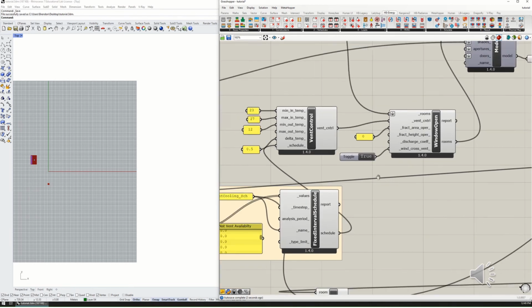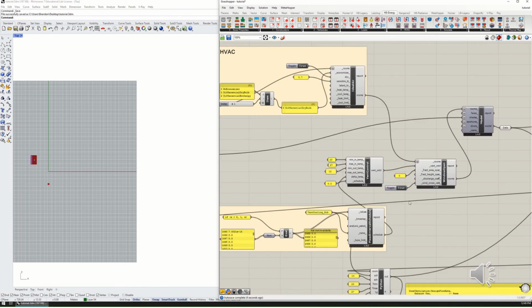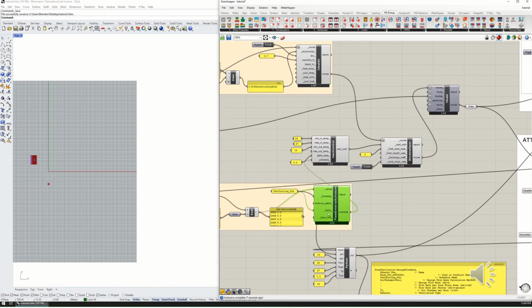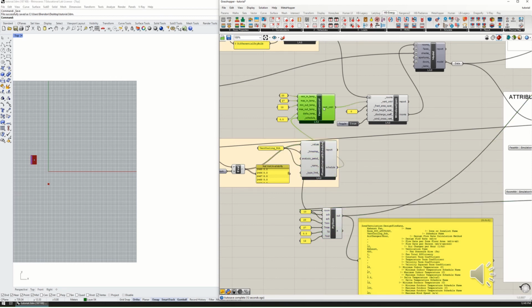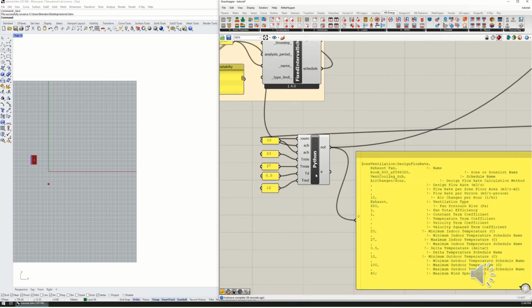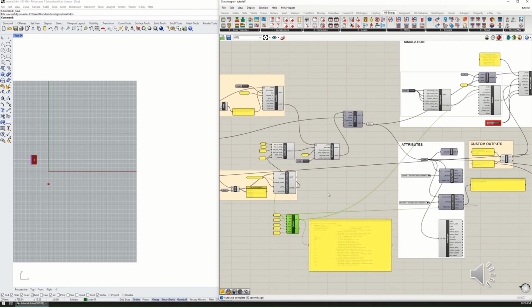The reason is we don't want to disable this completely because our vent cooling schedule that this fan is using is running through this window opening. And so even if this is zero, the ventilation cooling schedule will still be in effect. It'll be stored in the file. But if we get rid of this component completely, that ventilation schedule will not be written into the file, and so we won't be able to use it in this component here. I hope that makes sense.